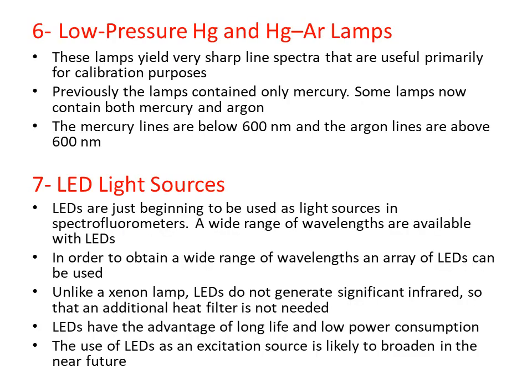Another light source is low pressure mercury and mercury-argon lamps. These lamps yield very sharp line spectra that are useful primarily for calibration purposes. Previously, lamps contained only mercury, but now some contain both mercury and argon. Mercury produces lines below 600 nanometers, while argon produces lines above 600 nanometers.